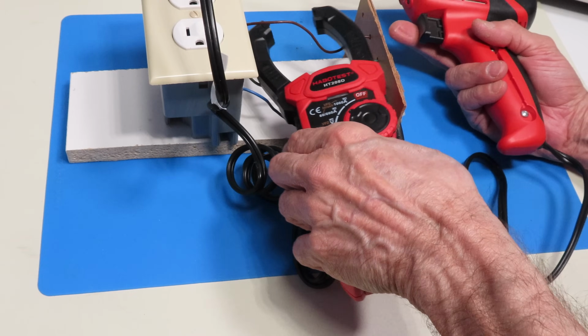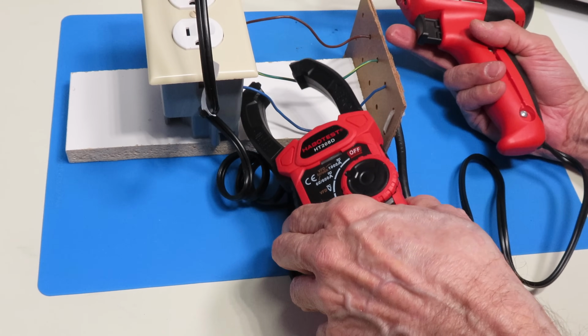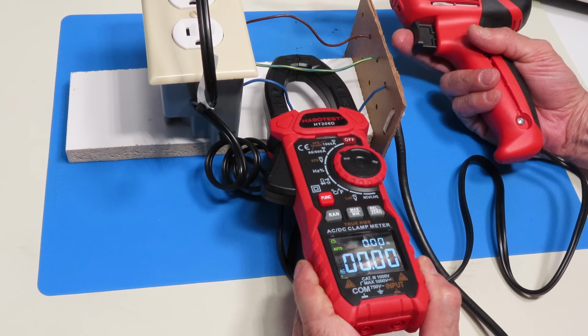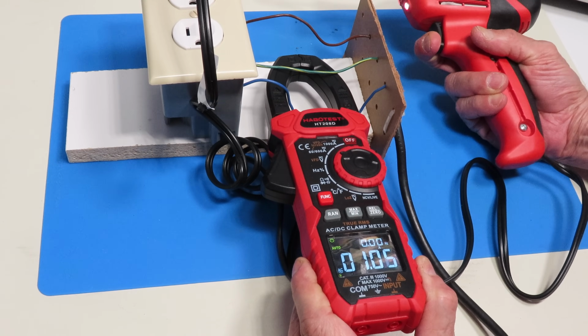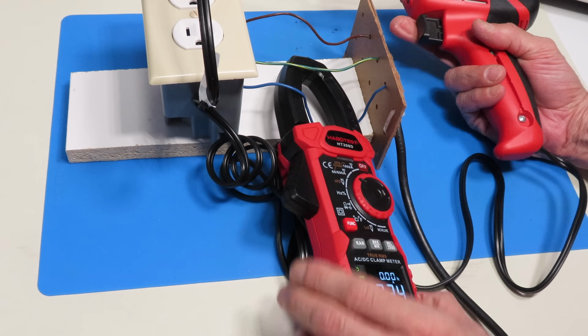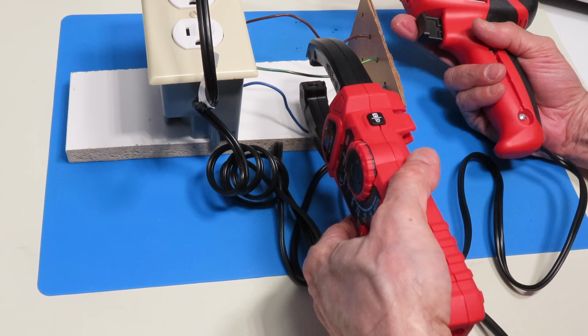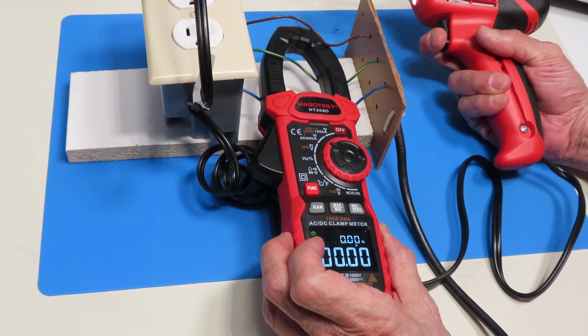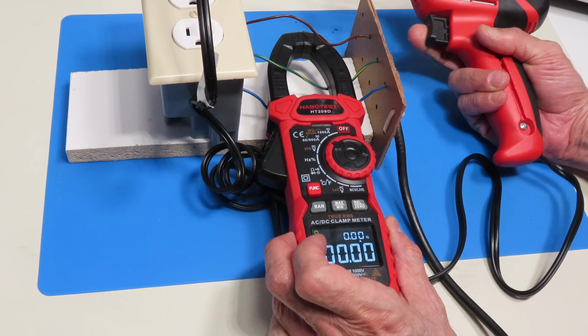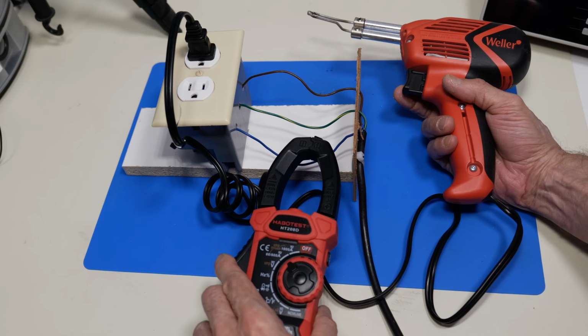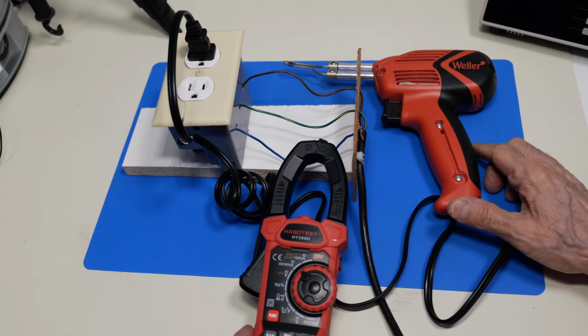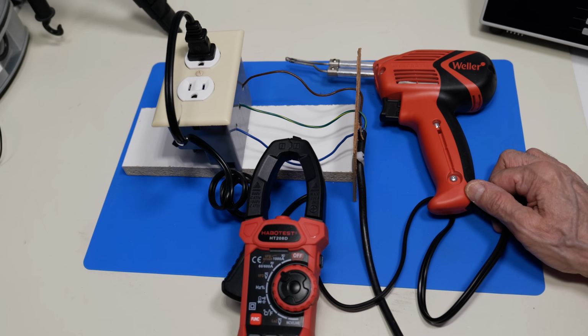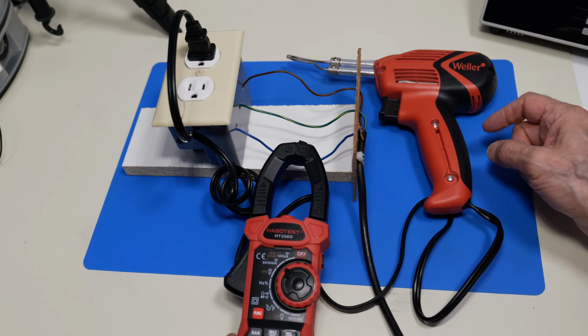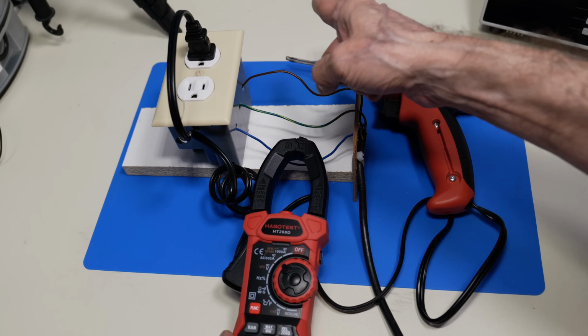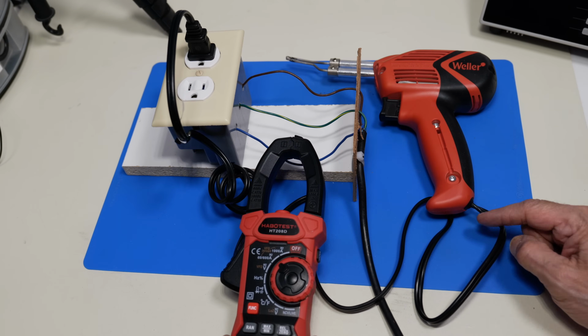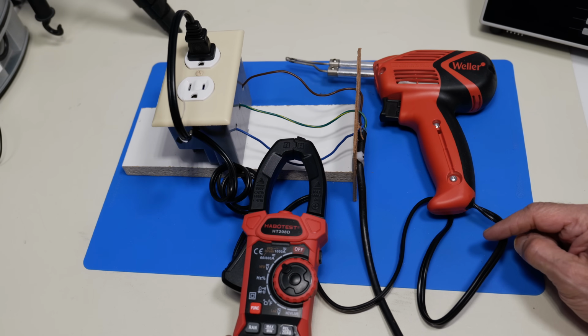You can also measure this down on the neutral side as well - it'll measure over there too, but of course it will not measure on the ground. You can't expect anything there, and naturally you don't get it. So inductive current sensing is a very handy and very safe thing to be able to do. Just remember, you need to be sensing one of the wires - if you try to do both, they'll cancel each other out and you won't get any reading at all.